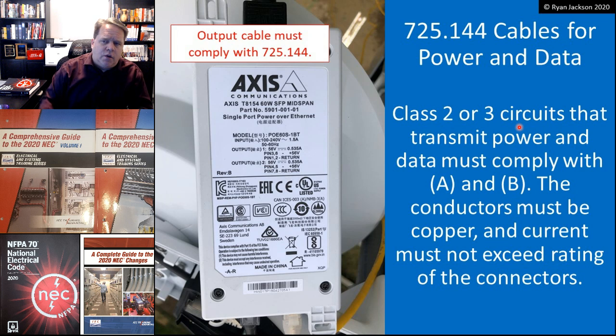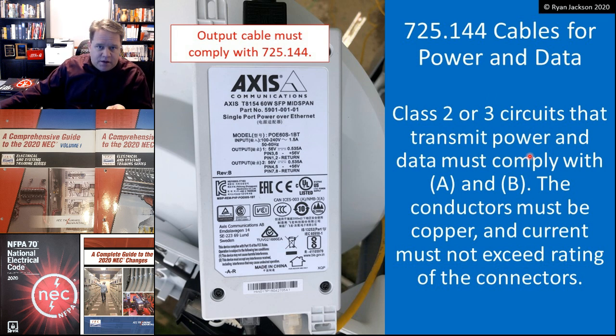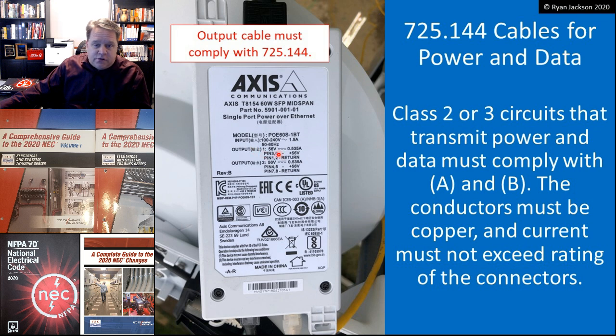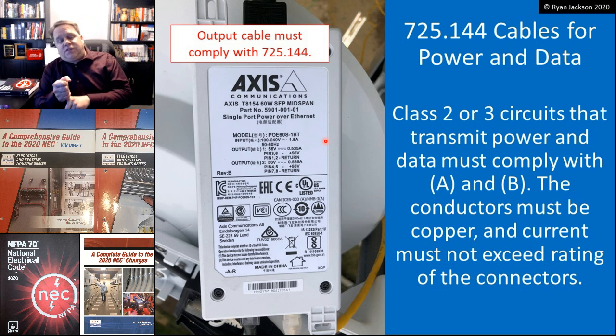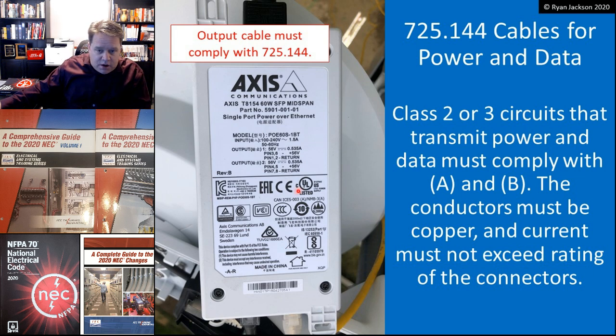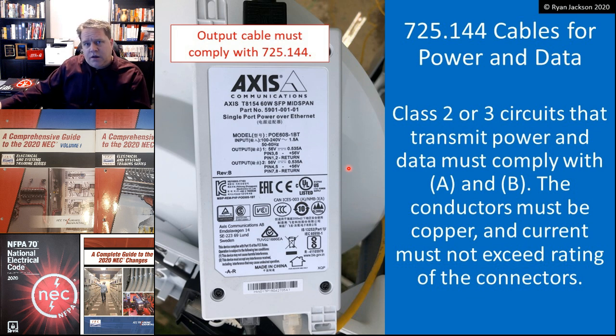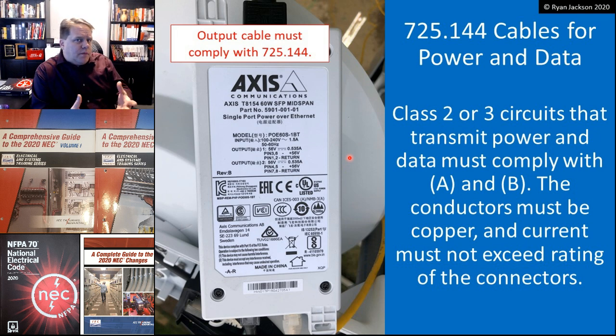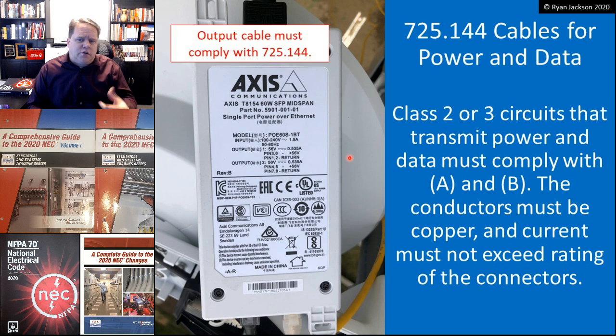Going back to 725.144: class 2 or class 3 circuits that transmit both power and data must comply with A and B. Here we have a single-port power over Ethernet power source with an input of 120 volts and an output of 56 volts at half an amp — low voltage, low current. This is a listed ITE power supply and is considered a class 2 power source. The conductors have to be copper, and the current must not exceed the rating of the connectors. We're talking about twisted pair cable, so aluminum conductors would be doubtful anyway.